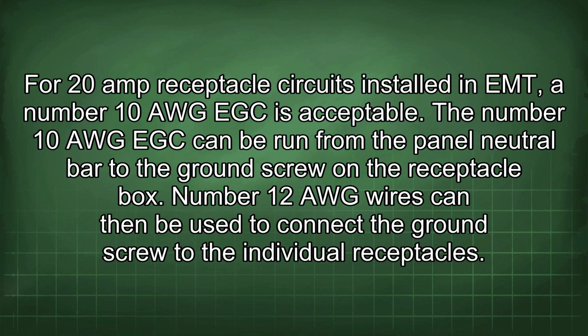For 20 amp receptacle circuits installed in EMT, a number 10 AWG EGC is acceptable. The number 10 AWG EGC can be run from the panel neutral bar to the ground screw on the receptacle box. Number 12 AWG wires can then be used to connect the ground screw to the individual receptacles.